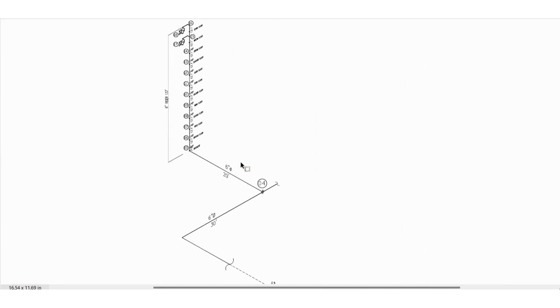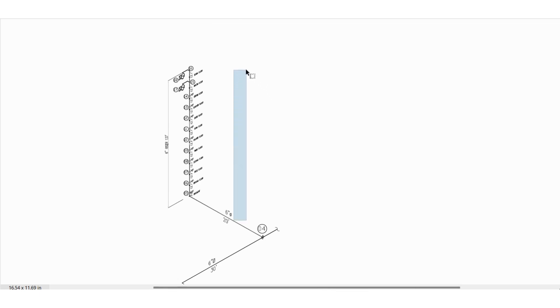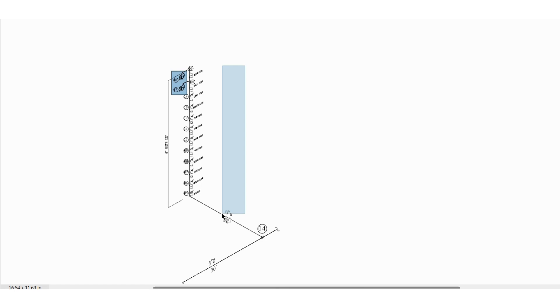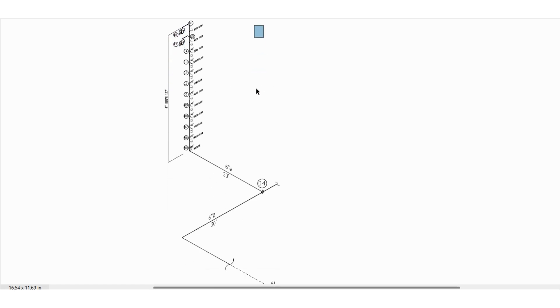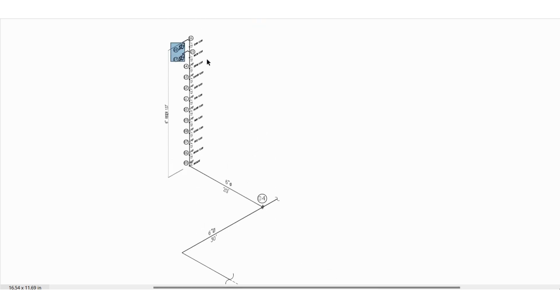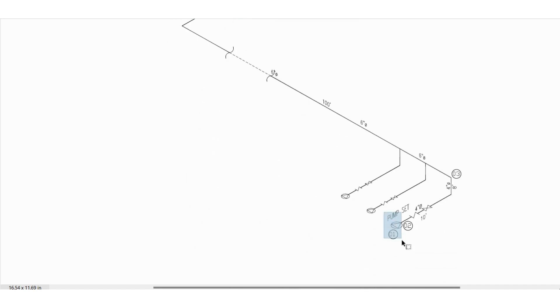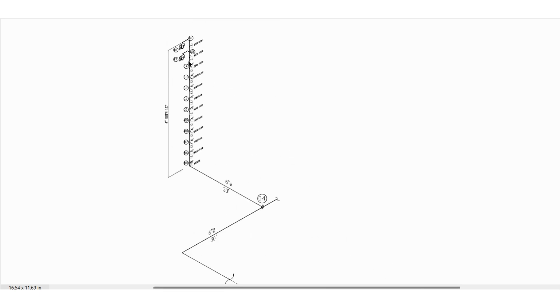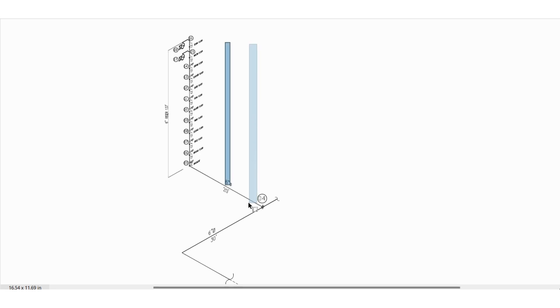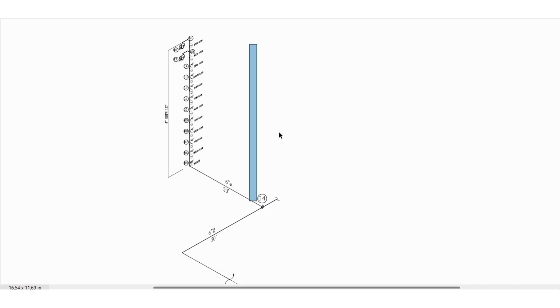I want to highlight: if you have another standpipe in this project also served by landing valves, then we need to consider 500 GPM from the remotest landing valve standpipe riser and 250 GPM from the other standpipe. So the demand will be 750 GPM if we have two standpipes. As per NFPA 14, we need to consider 750 GPM as the system demand in the calculation. You can go through NFPA 14 for more details. If you have three standpipe systems, check NFPA 14 for the answer.